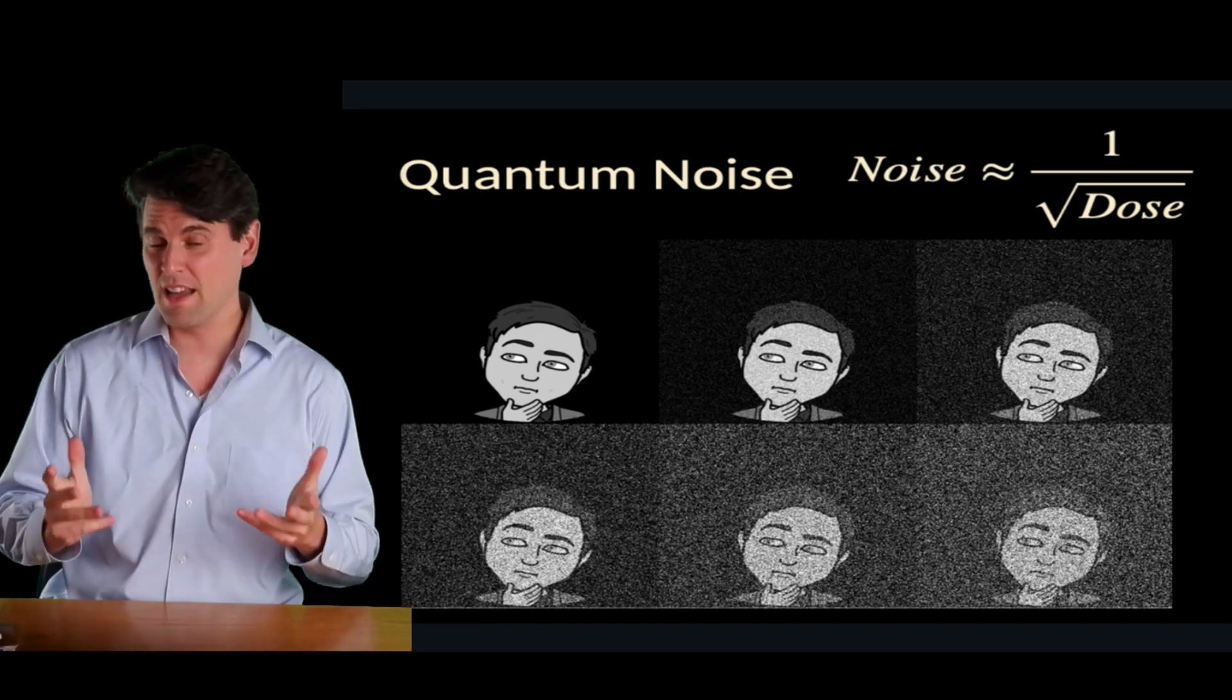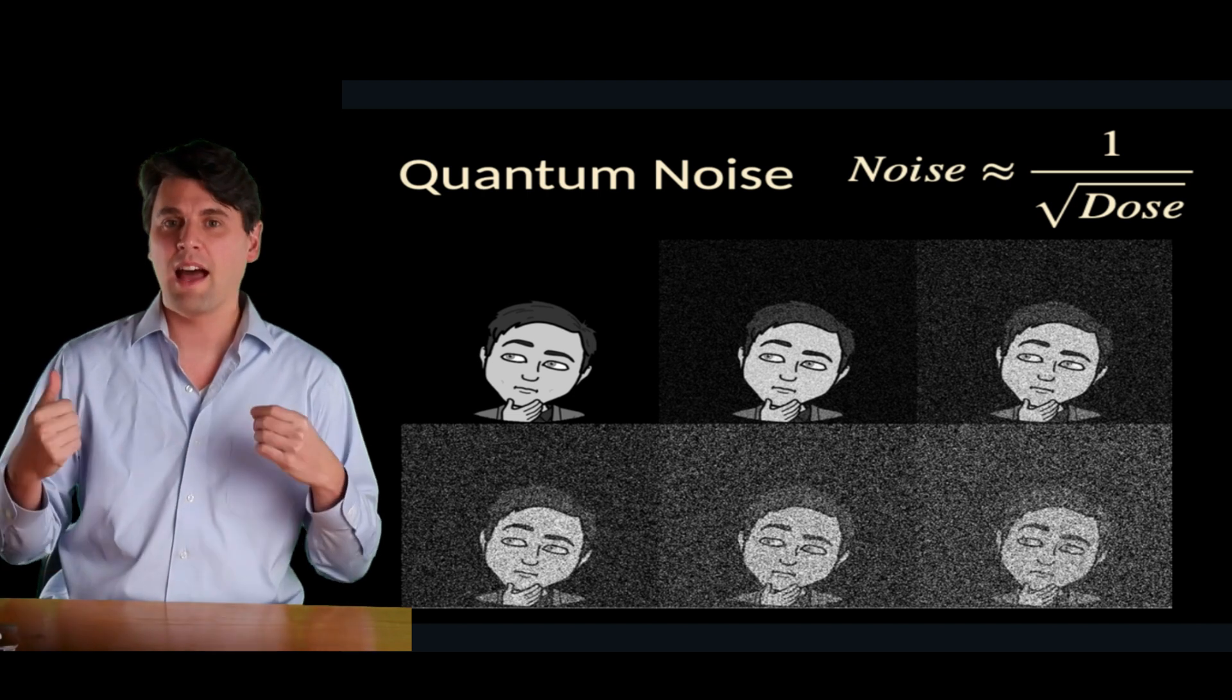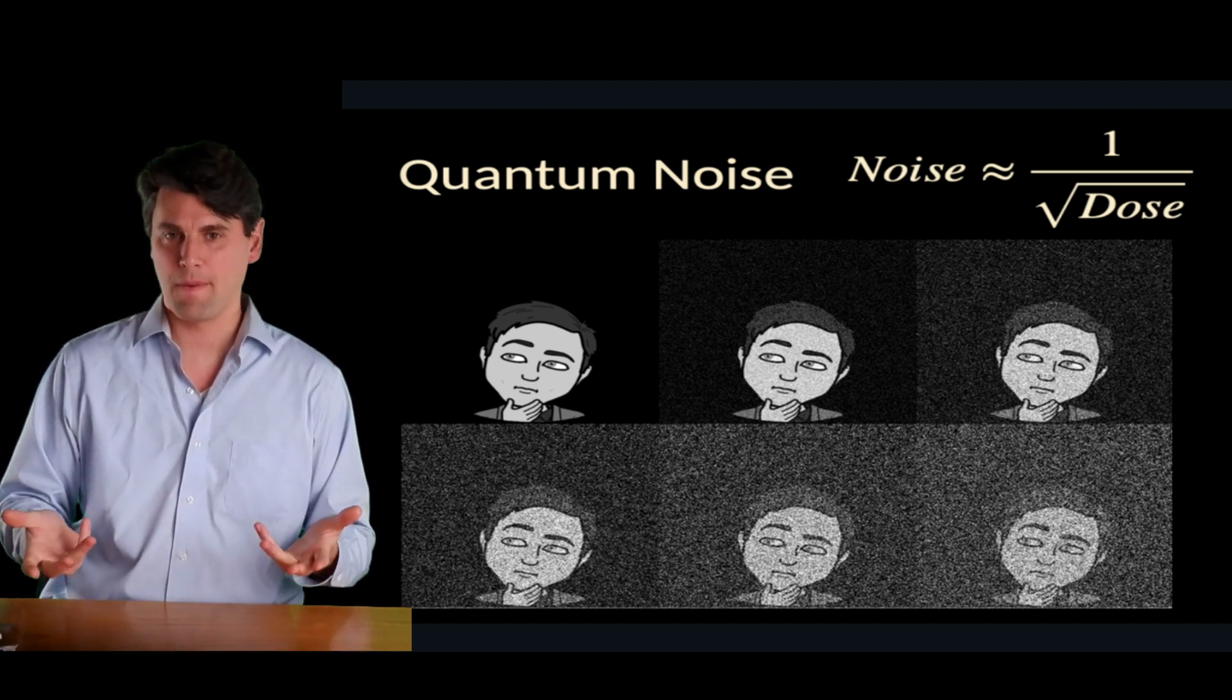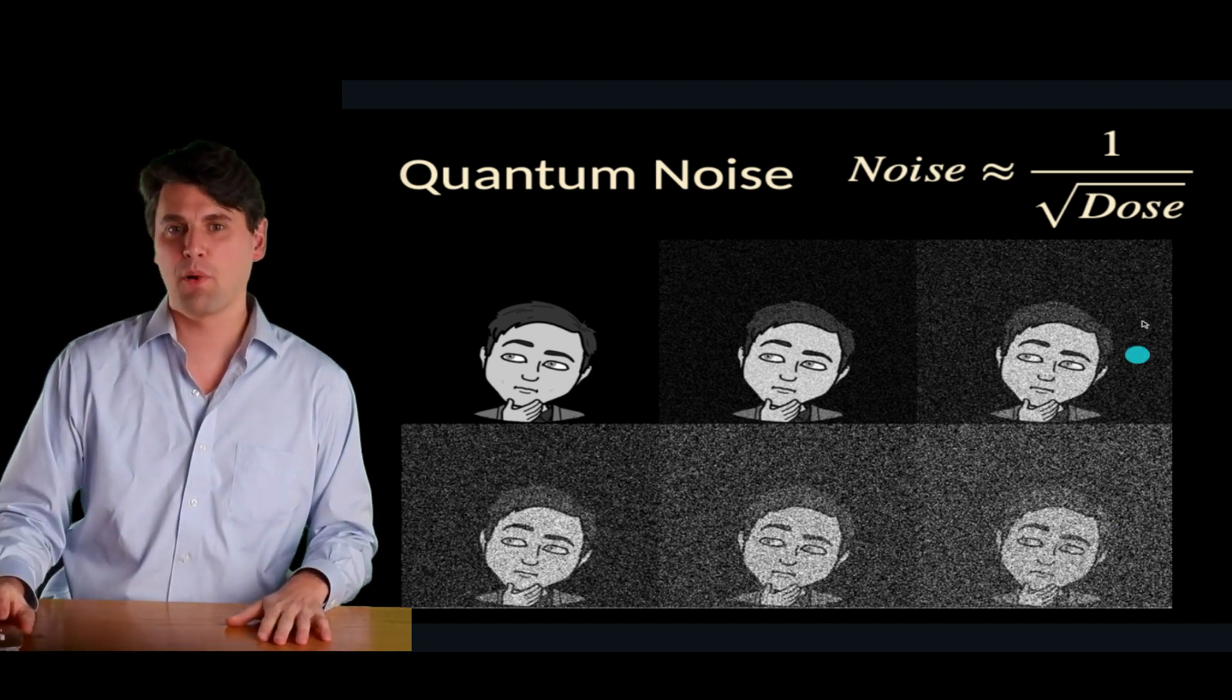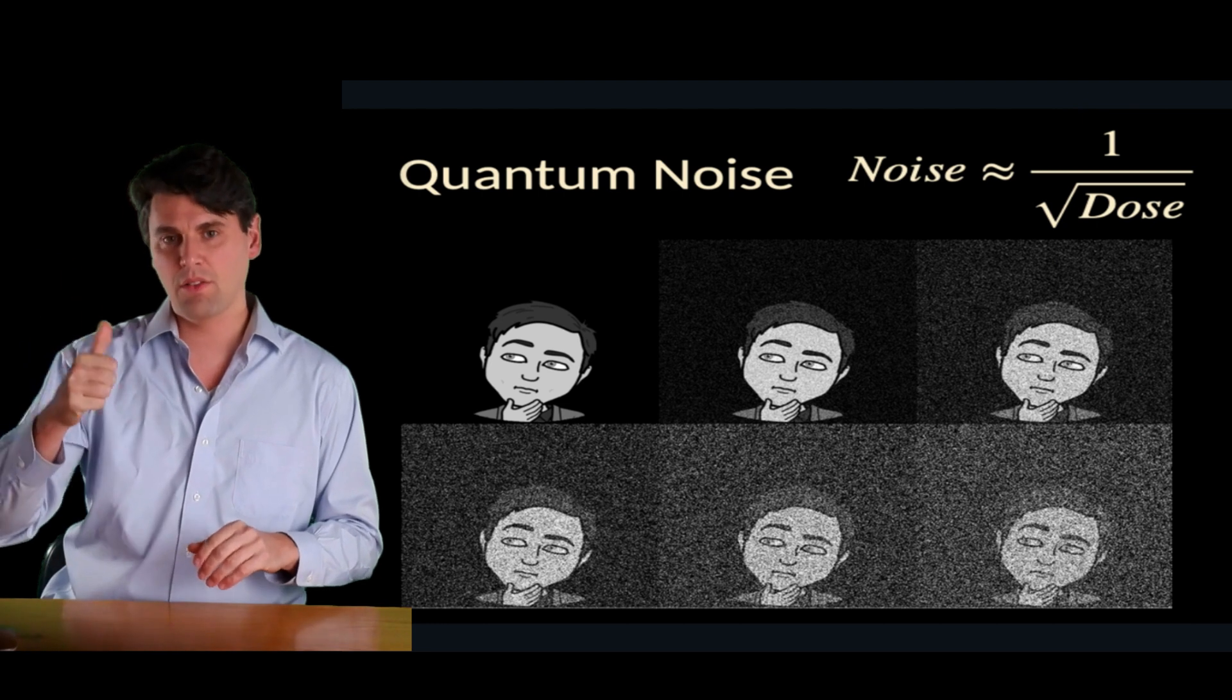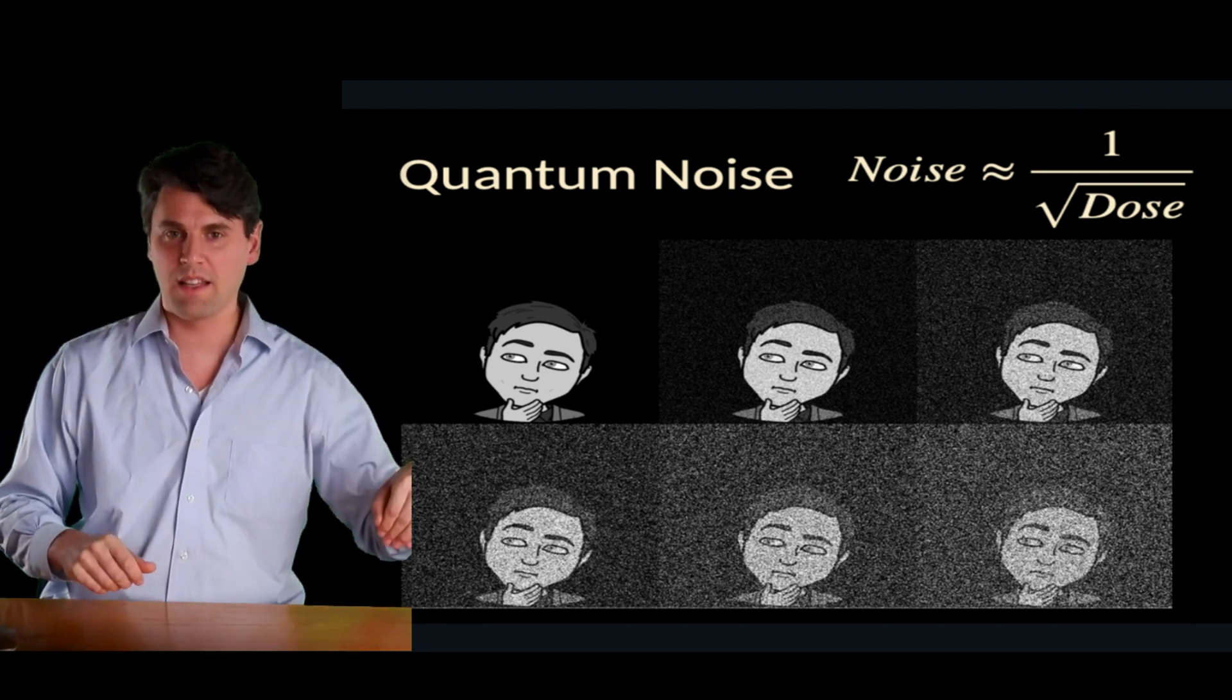The relationship we'll cover in more detail in other videos, but as the dose goes up, the noise is going to go down. So you can see here in this proportional relationship, the noise goes inversely like the square root of the dose. So as the dose continues to go up, the noise is going to continue to go down.